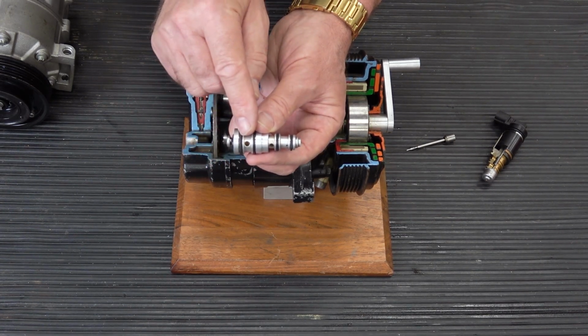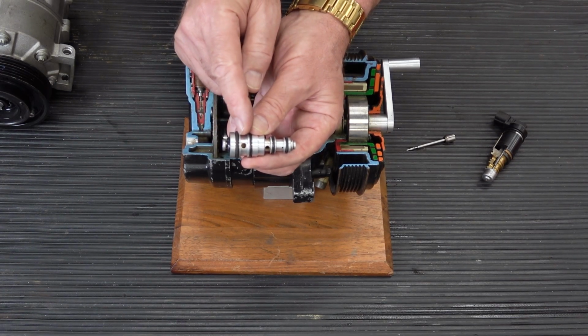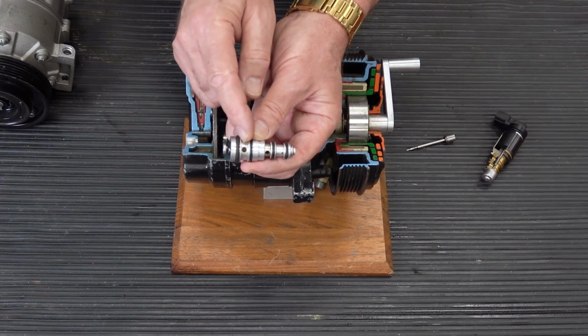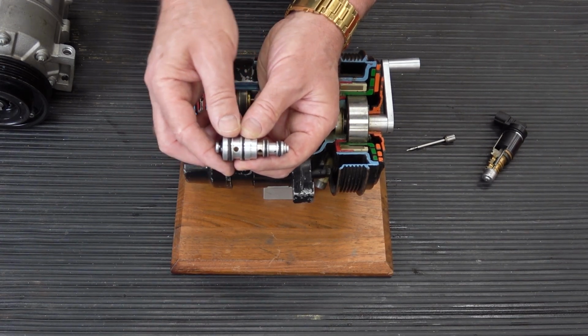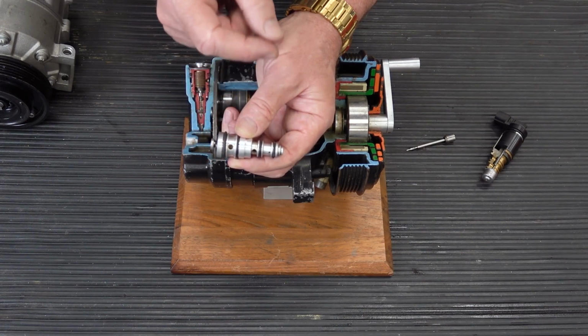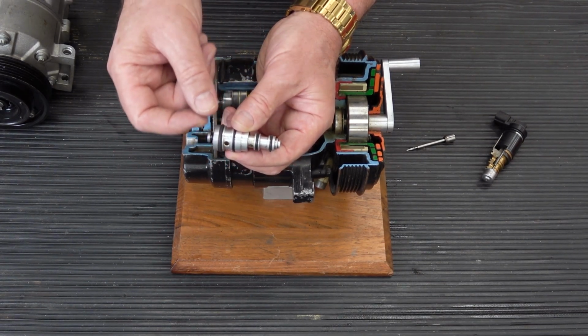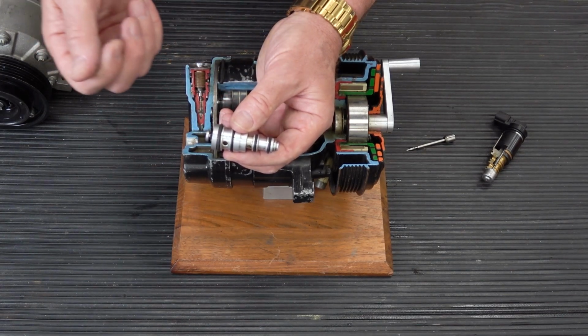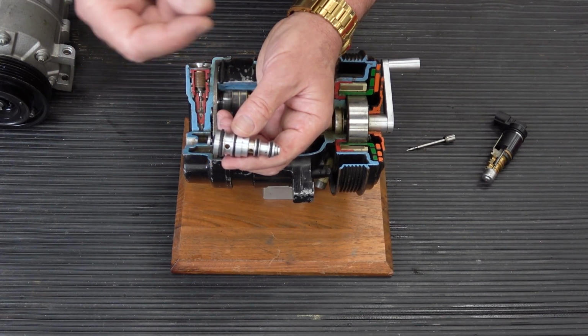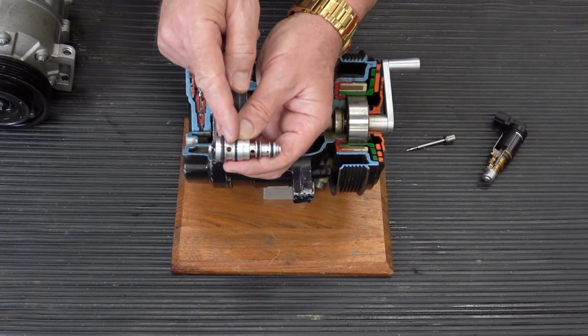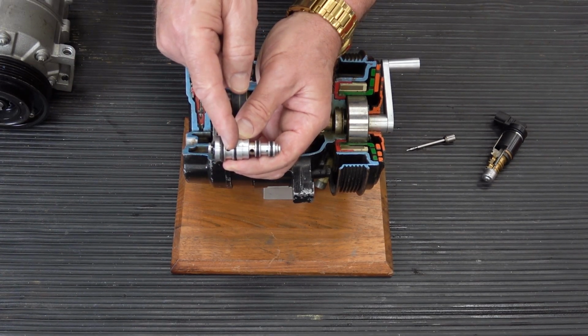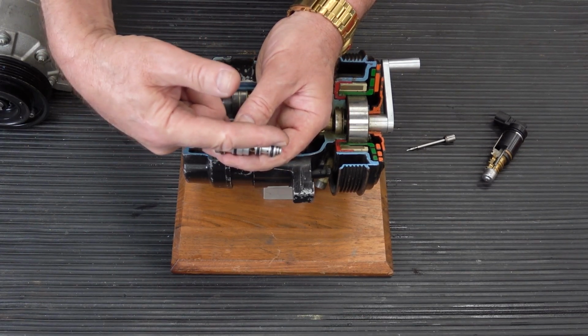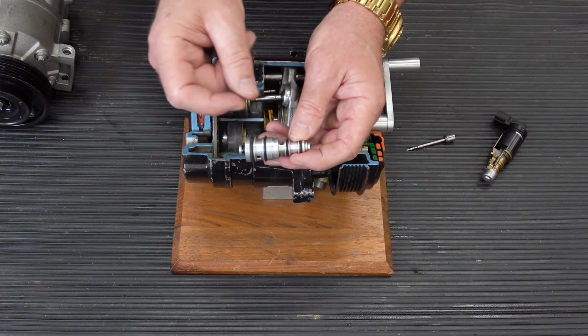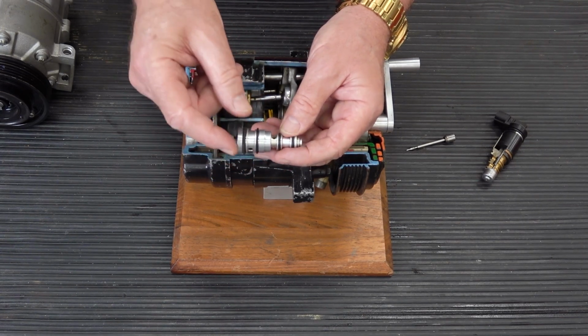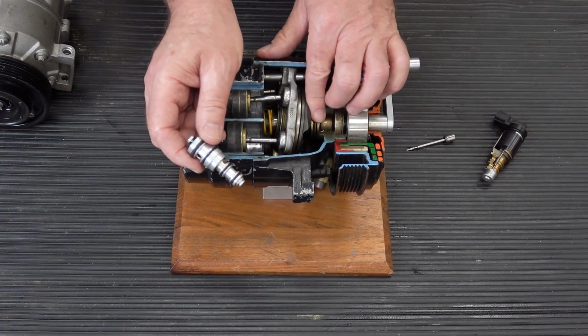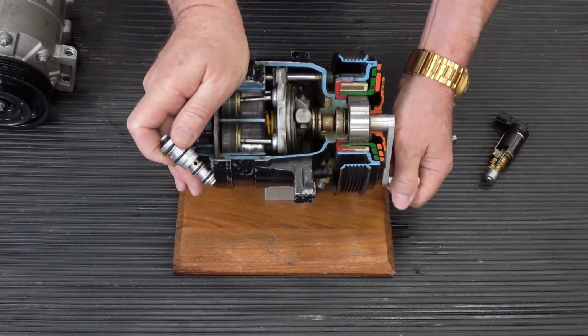The way this works, there's a pneumatic, pressure-sensitive bellows inside the valve, and this area of the valve between these two O-rings is exposed to suction side pressure. Suction side pressure, of course, is a function of how much heat load is on the system. If I turn the blower on to high speed, low side pressure is going to increase because it's absorbing more heat energy. That increased pressure will act on the pneumatic bellows inside, and it will move a rod, a pintle, inside here. And so that's how we control the pumping displacement of this compressor. By sensing suction side pressure, we can adjust the pumping output of the compressor.